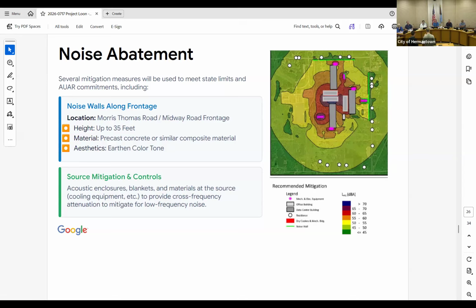To address your question earlier about sound getting attenuated for those properties to the south, the reason we don't want to build a wall there is because it wouldn't actually be effective. That's one of the lowest areas of the site, so we want to flex some of our stronger mitigation muscles there. We want to think about how we can mitigate noise at the source, whether through enclosures, acoustic blankets, or choosing a quieter piece of equipment. Pulling on those levers will help those properties to the south more than building a wall that isn't actually blocking the line of sight, because the properties are set higher in the ground. If you're already above it, then you're over it anyhow.